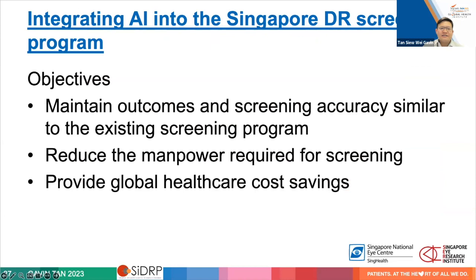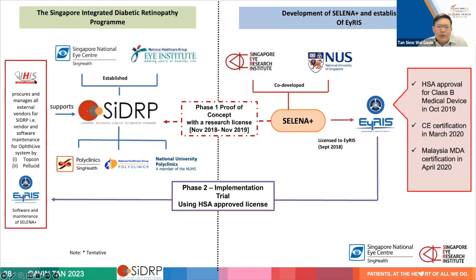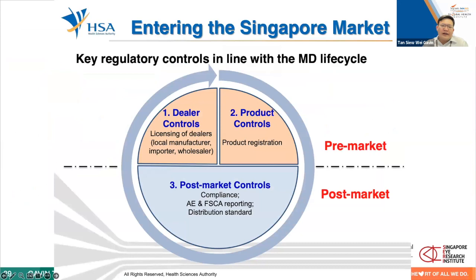Once you have an AI algorithm, you need to figure out how to use it — something published in a paper is of no use if it doesn't help patients. Our objectives for integration were: ensure screening accuracy was similar to the existing program, demonstrate reduced manpower requirements, and look at cost savings. The implementation process was not straightforward — we had to get HSA approval as a medical device, which an academic institution generally cannot do alone, so the licensing was spun off into a startup company that handled all the compliance and regulatory requirements.